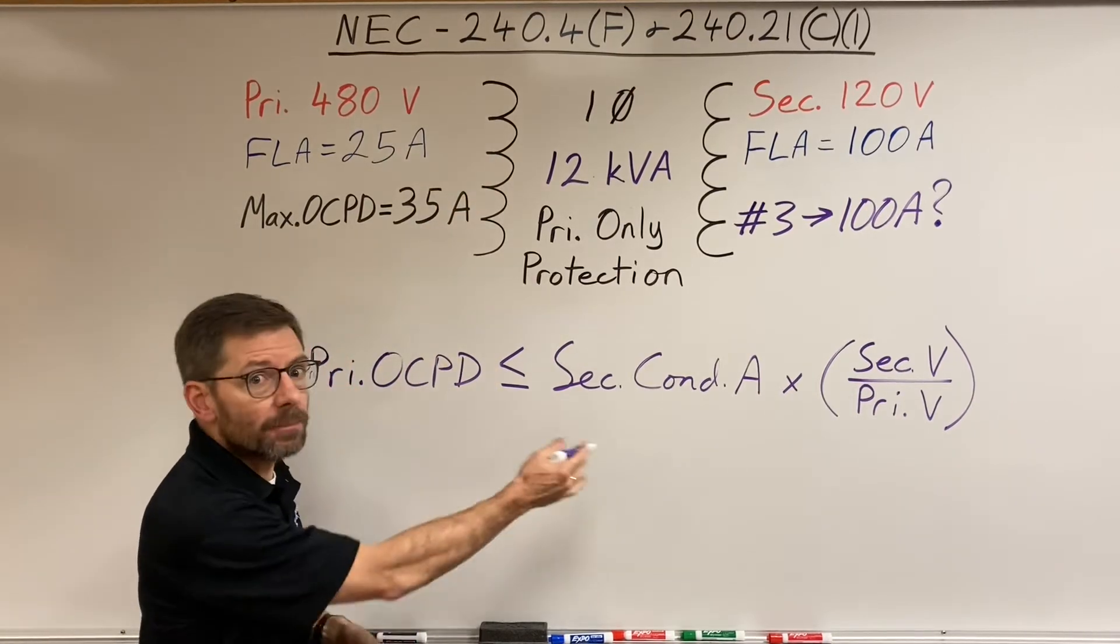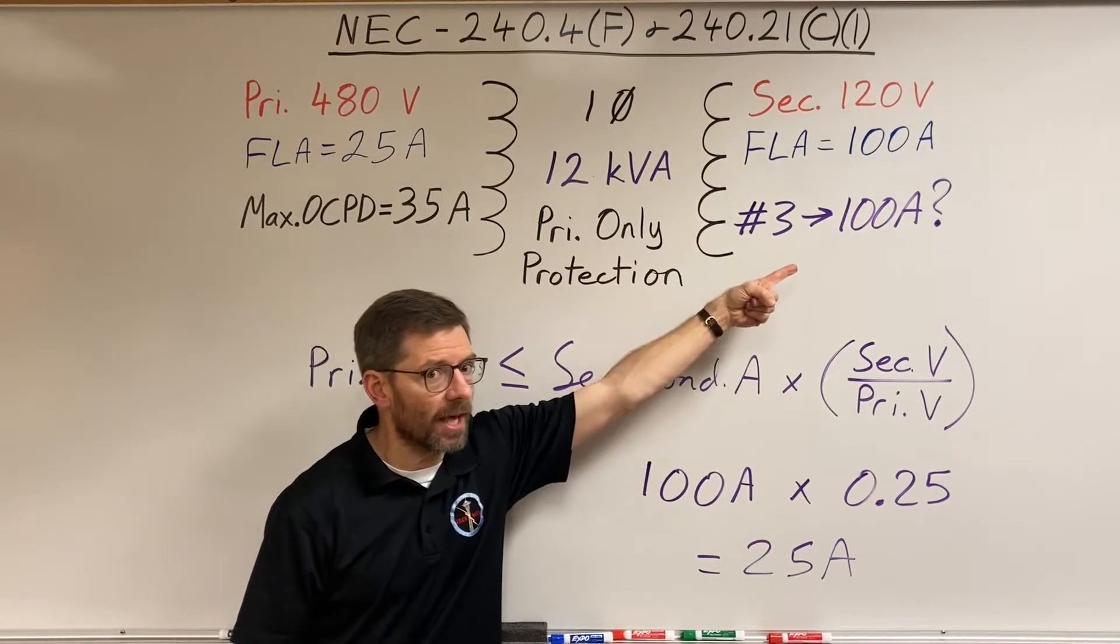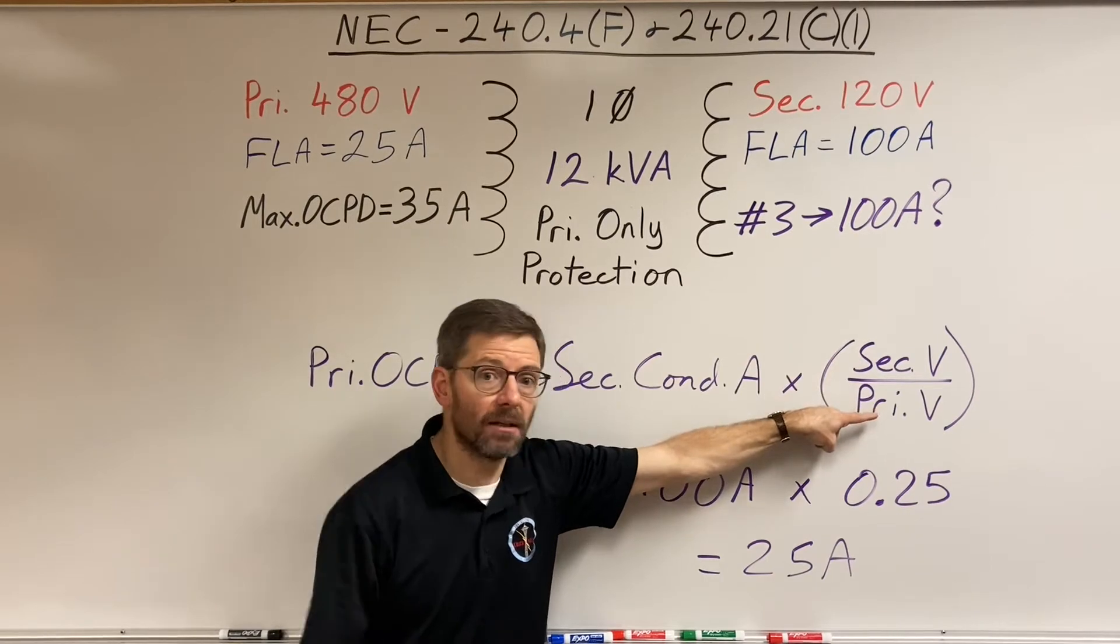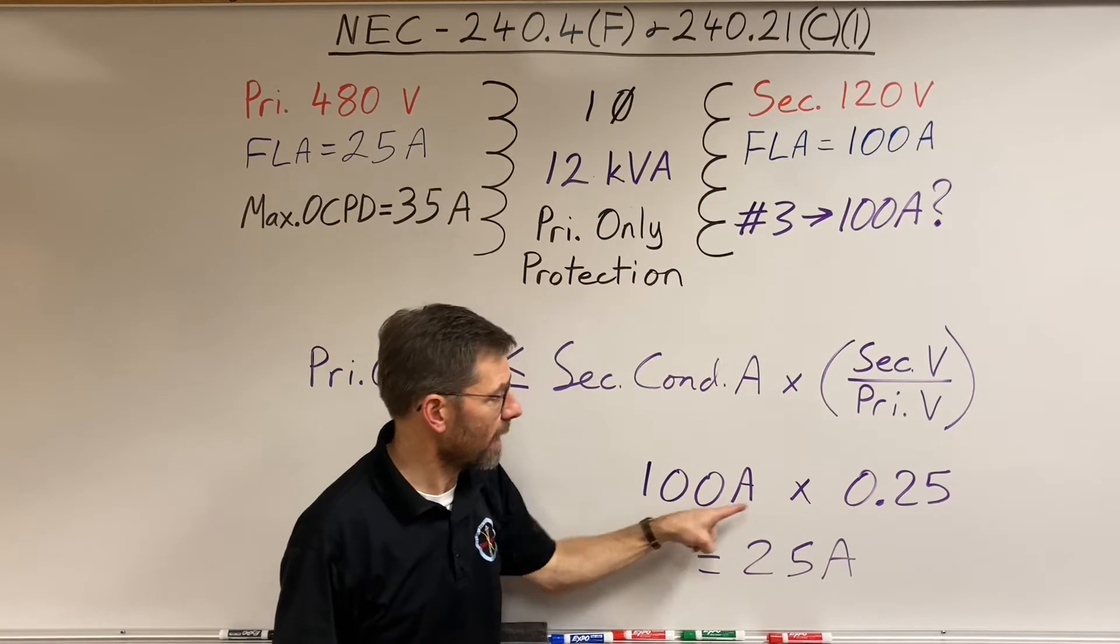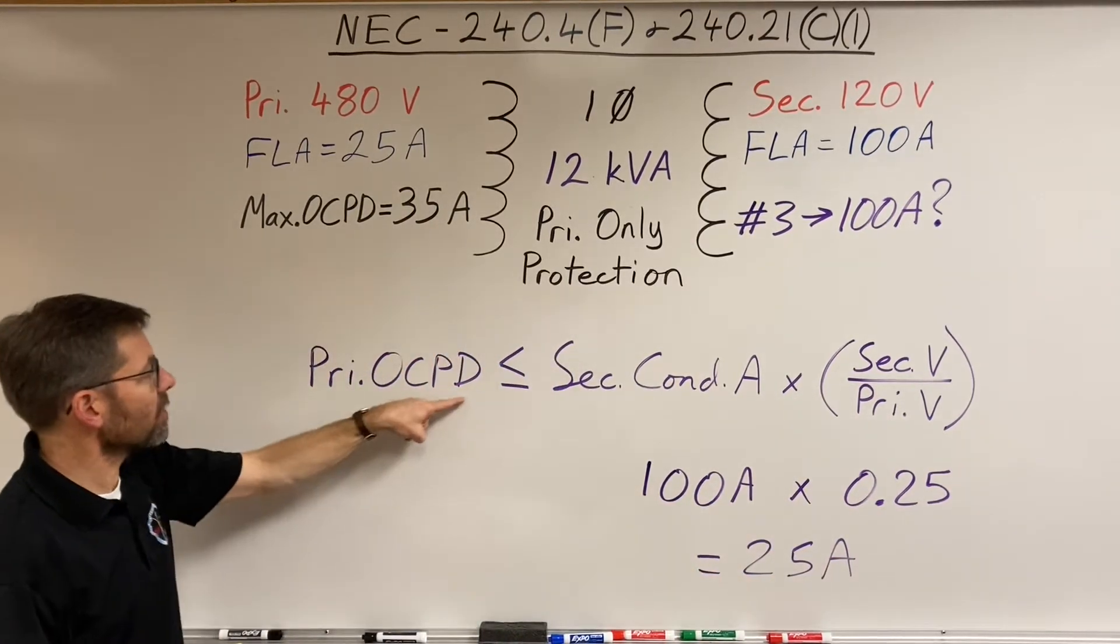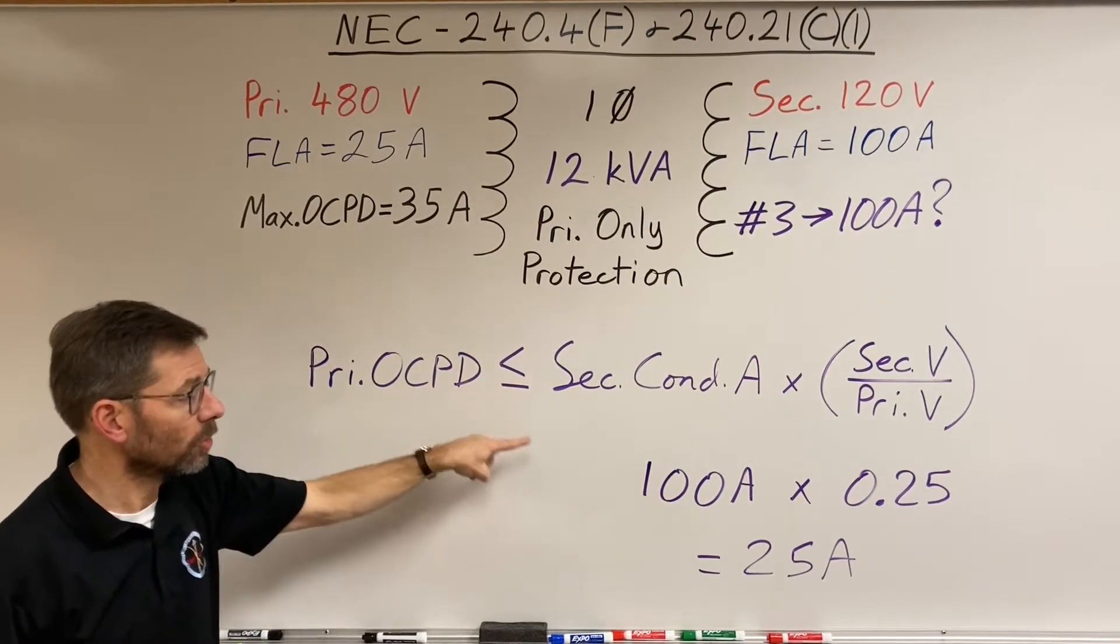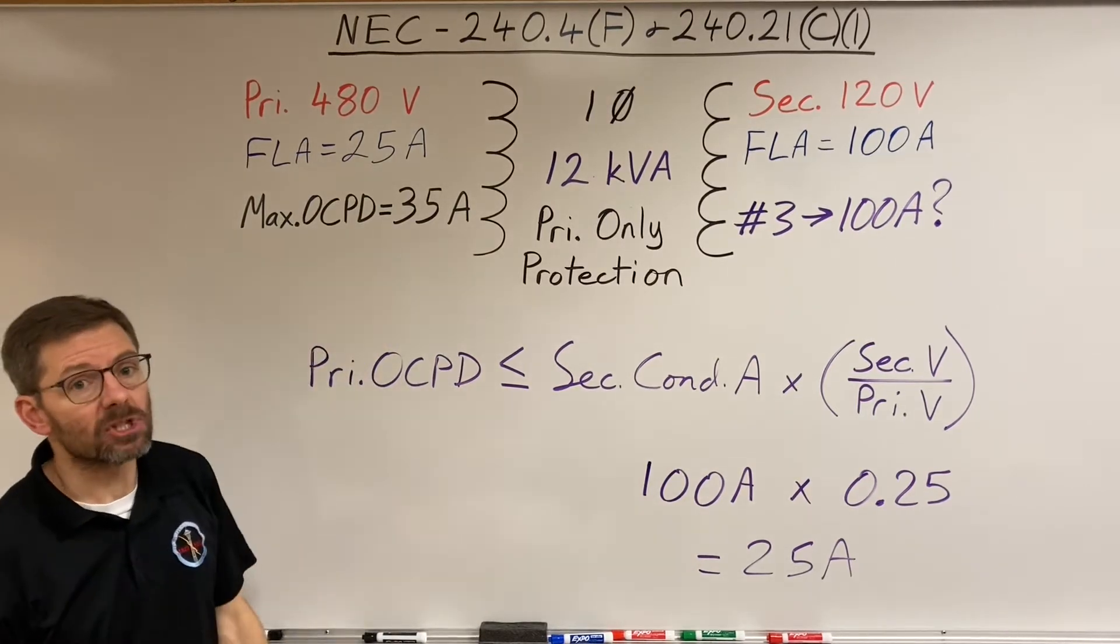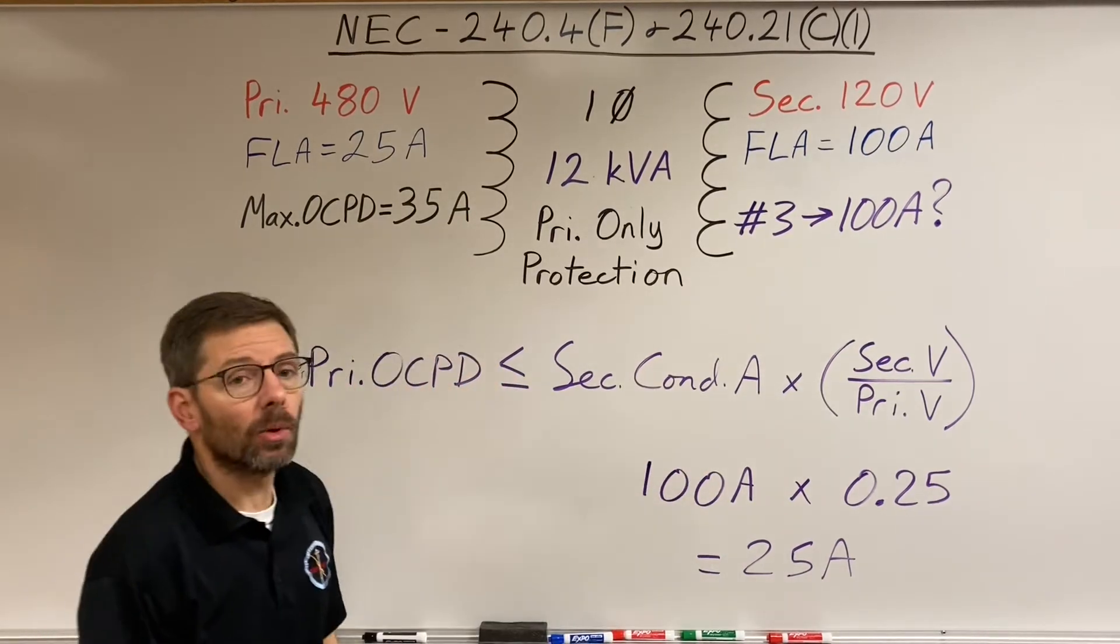My secondary conductor ampacity is 100 amps. The ratio is 120 divided by 480, so that's a quarter. 100 amps times a quarter is 25 amps. It's saying that this primary overcurrent protective device has to be less than or equal to 25 amps. Now 35 amps is more. That's if I want to use a number three. So that's not going to work.